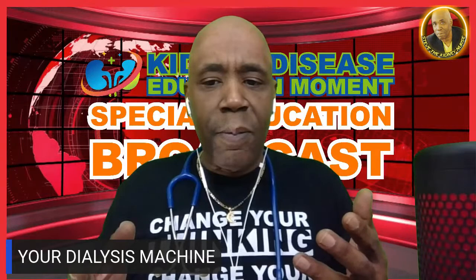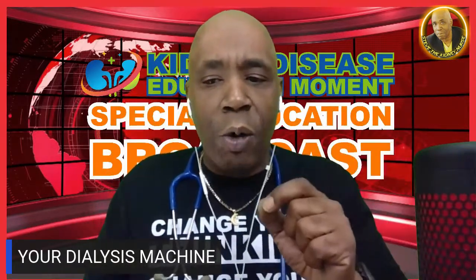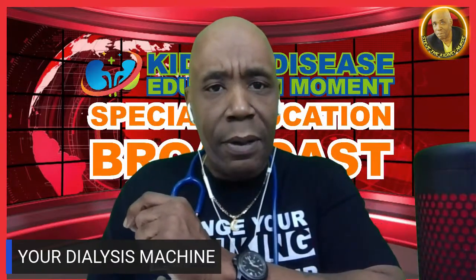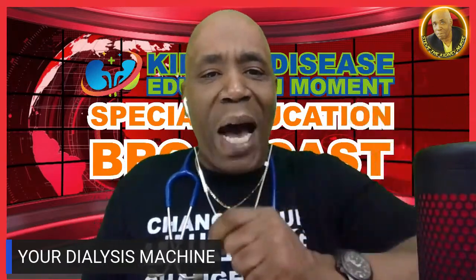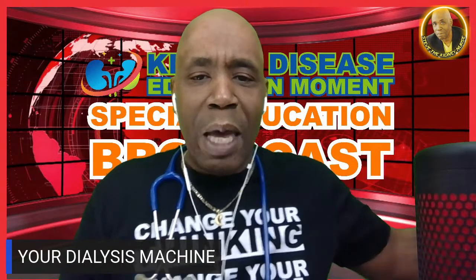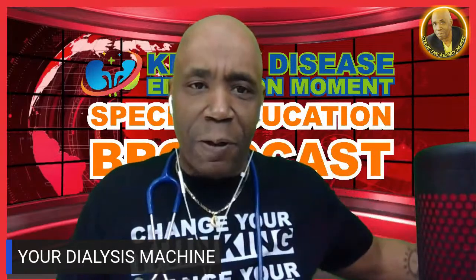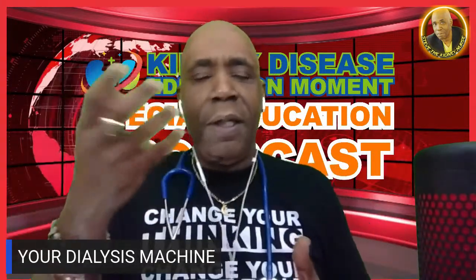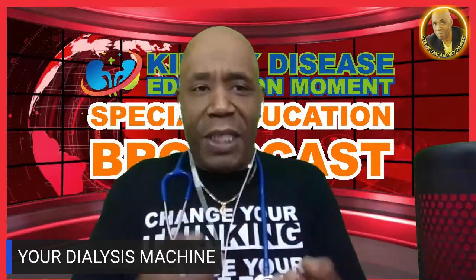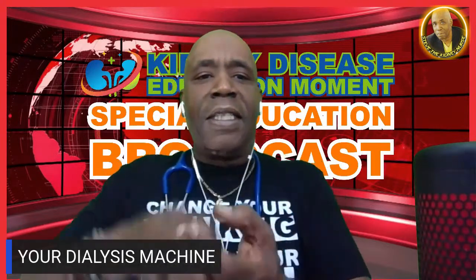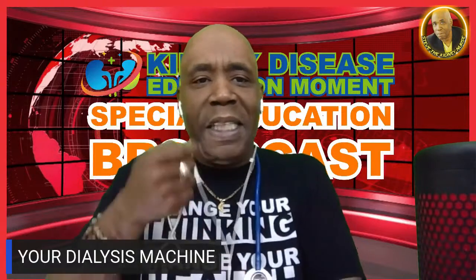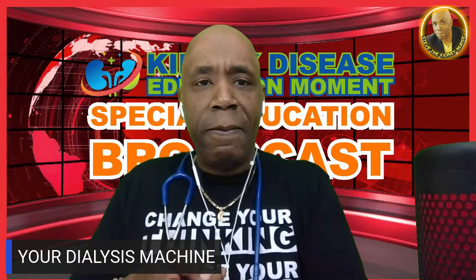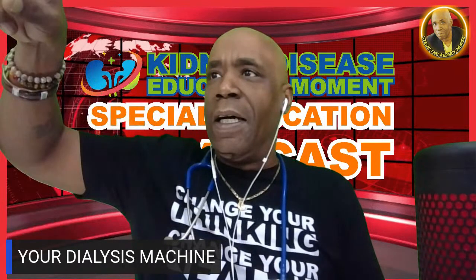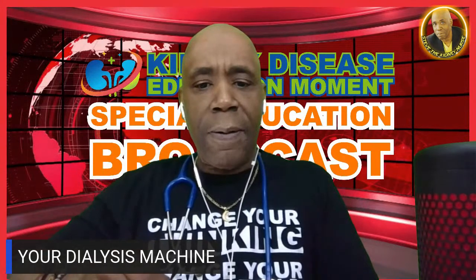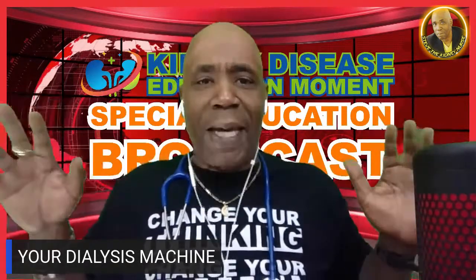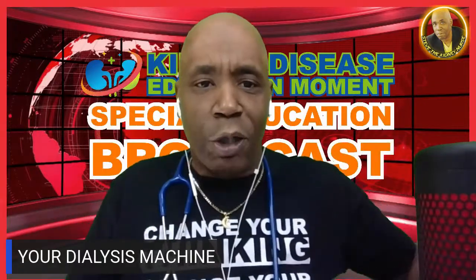Now, the dialysate must have a pH close to that of normal blood, so it does not change the body pH. And bicarbonate replaces the body's stores of buffer. That's why the staff is supposed to use a meter called the Phoenix meter. Patients don't see it, but before patients come in, the staff is supposed to check the pH of the dialysate. They get that out of the dialysate hoses. But you don't see that as patients, because all that's supposed to be done before you walk through the door.